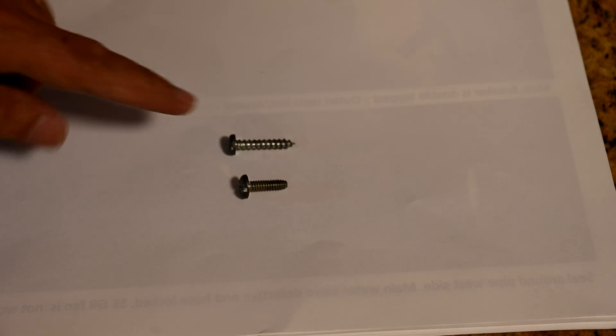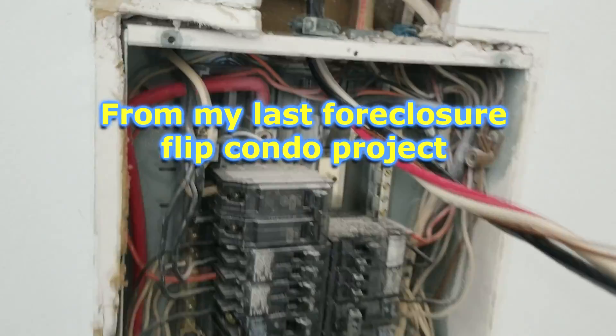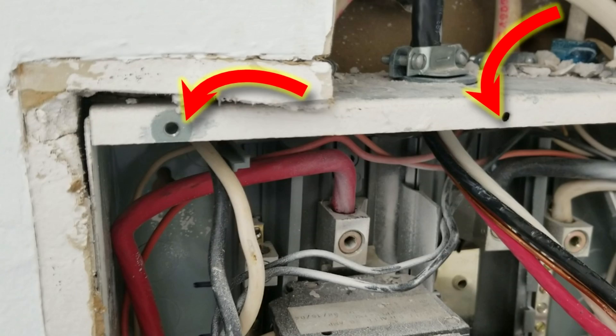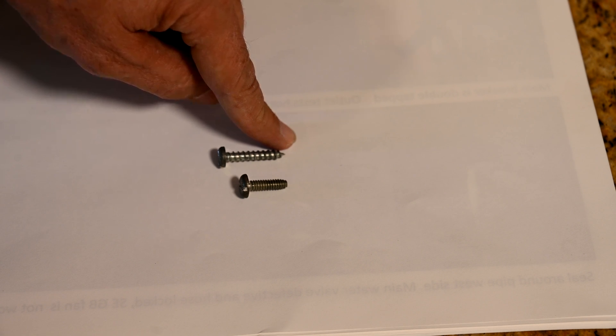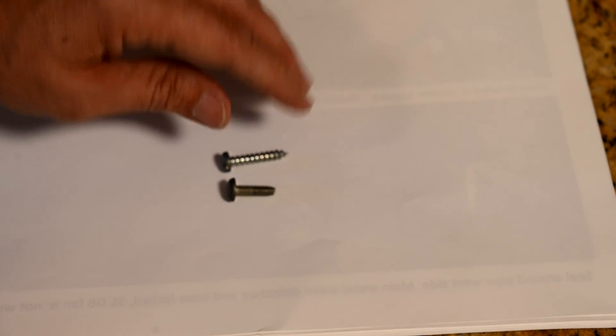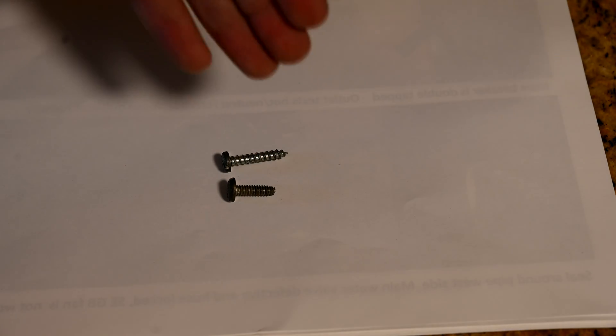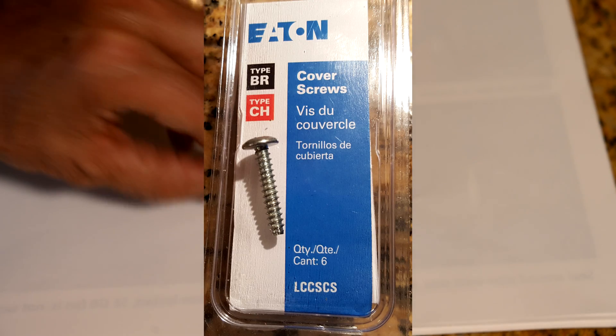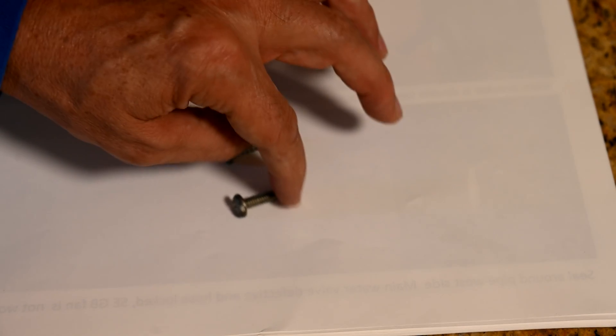With these electrical panels, right where the screw goes in, where you saw us pull them out of the wall, there's all sorts of wiring back in there — wiring that loops around inside the electrical panel. If you have a pointed screw going through there, you run the risk of piercing one of those wires. And if one of those wires is a black wire carrying 120 volts and a kid touches the screw on the outside, which is on the wall next to the refrigerator, they could get shocked and killed. It's incredible how just a little bit of stupidity can cause a lot of problems. This was done by a handyman. They should be going to Home Depot and buying the correct Eaton screws — whatever screws match this size and shape with a flat tip — so they're not causing a potential fatality.